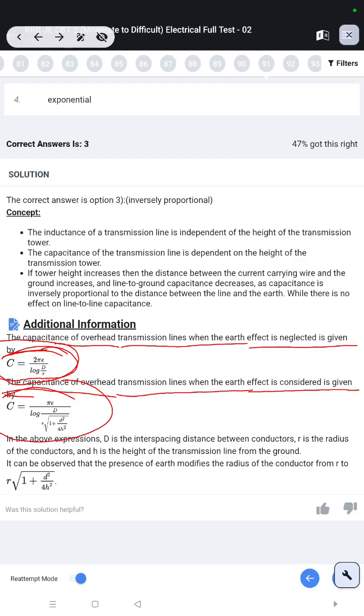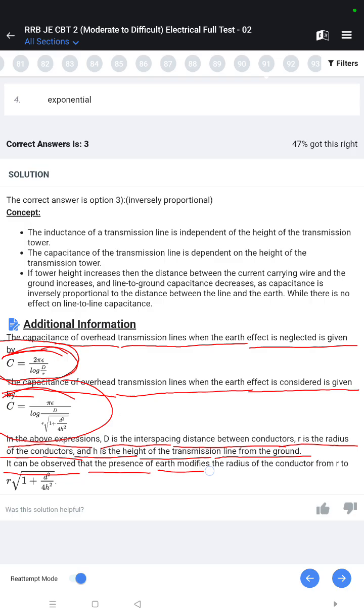In the above expression, d is the interspacing distance between conductors, small r is the radius of the conductors, and h is the height of the transmission line from the ground. It can be observed that the presence of earth modifies the radius of the conductor from small r to small r into √(1 + d²/4h²).